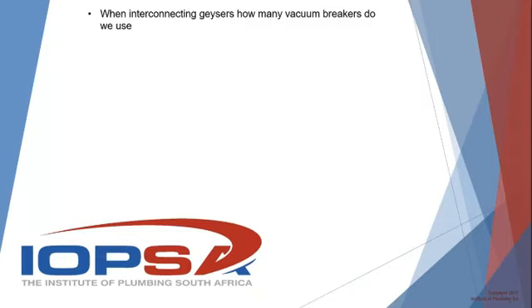Richard, can I just jump in there? We can refer the guys to figure 8 in SANS 10106 when they're talking about pre-feeding or preheating systems. There's a nice diagram of what those preheater systems look like. And they've got the requirement, like you said initially, that you need one on the hot and cold. On that preheater solar system, they actually share one down the middle between the hot out and cold in. But there's a nice diagram that gives you all the elements and all the descriptions in figure 8 in 10106. You can have a look at that.